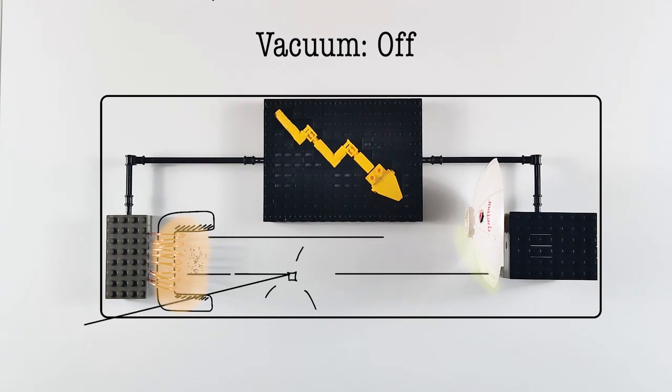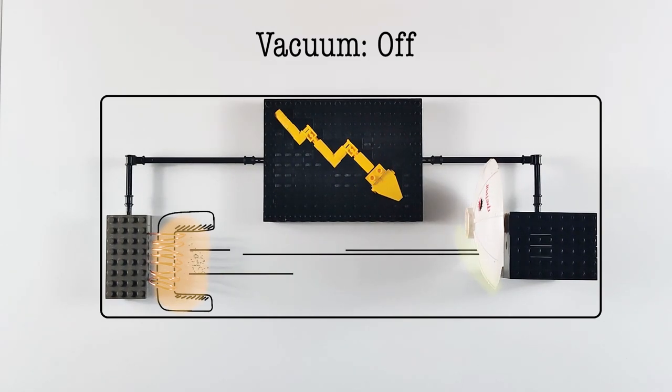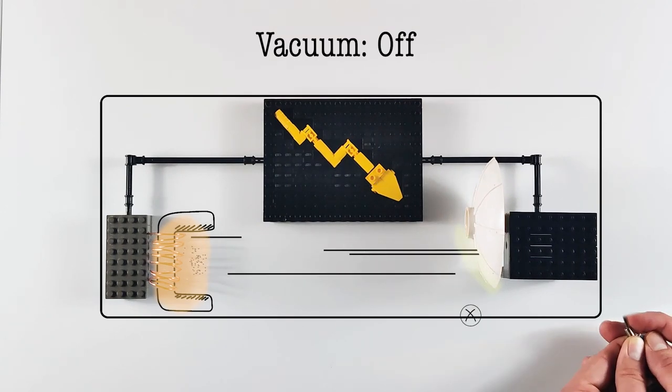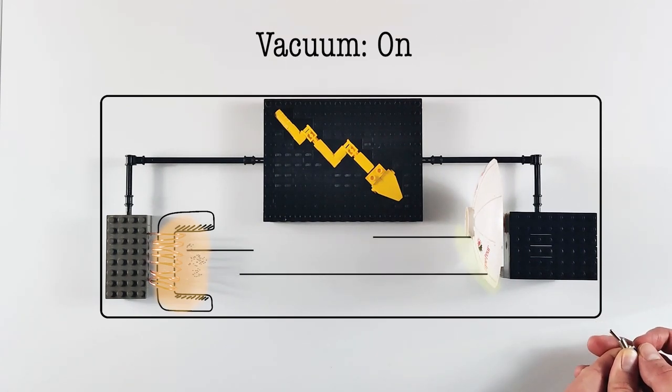The whole process takes place in a glass envelope, from which practically all air has been removed. The vacuum in the tube is crucial, because we would like all the accelerating electrons to reach the anode, not to lose their energy when bumping into gas particles. As a result of such collisions, electrons would run everywhere within the tube, instead of going straight to the anode.